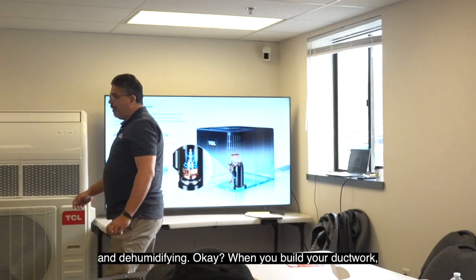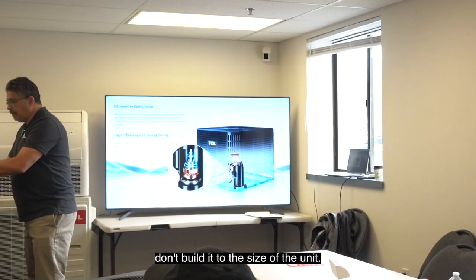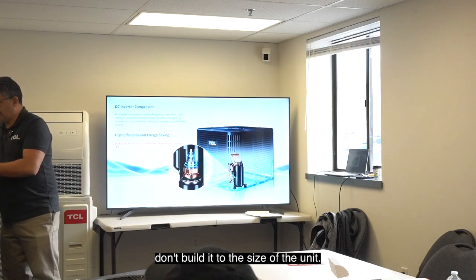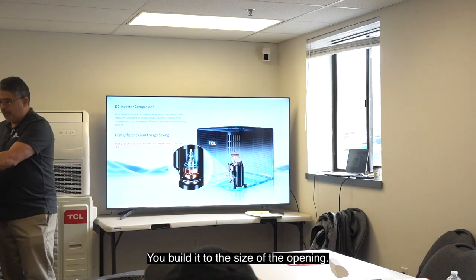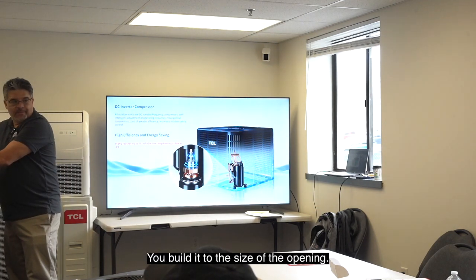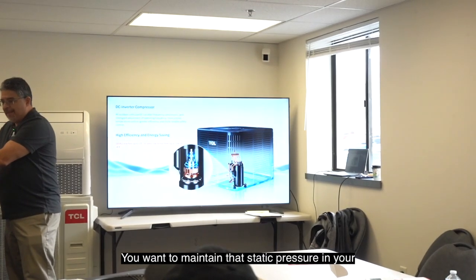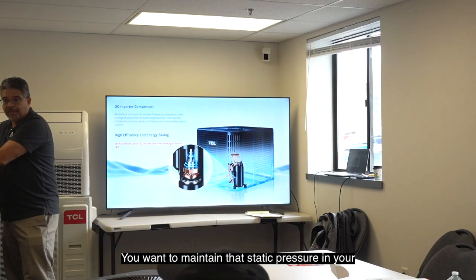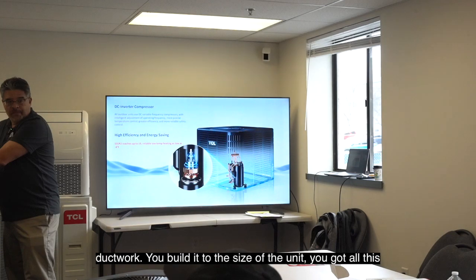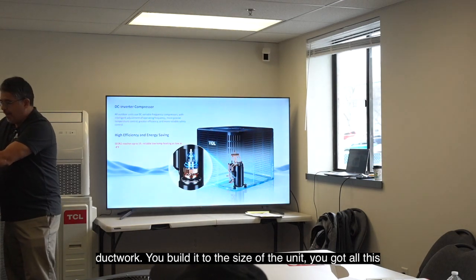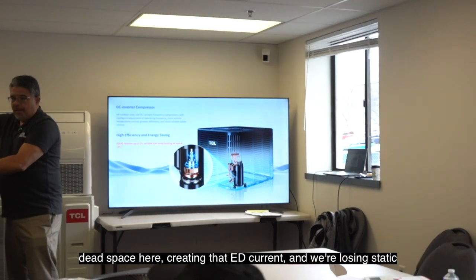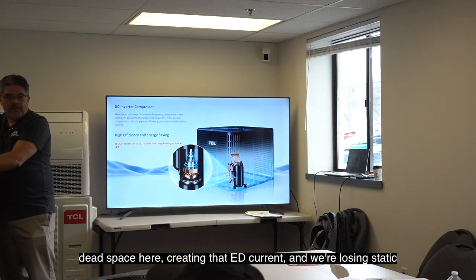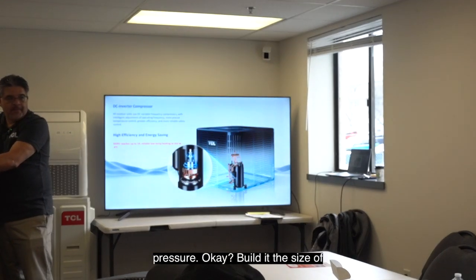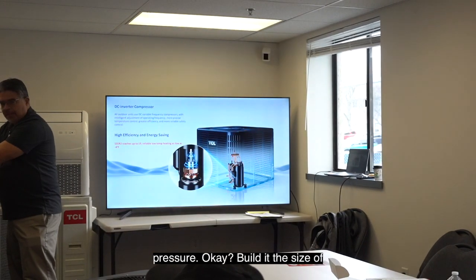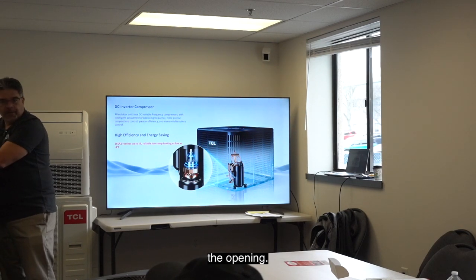Okay, when you build your ductwork, don't build it to the size of the unit. You build it to the size of the opening. All right, you want to maintain that static pressure in your ductwork. If you build it to the size of the unit, you got all this dead space here, creating that eddy current, and we're losing static pressure. Okay, build it the size of the opening.